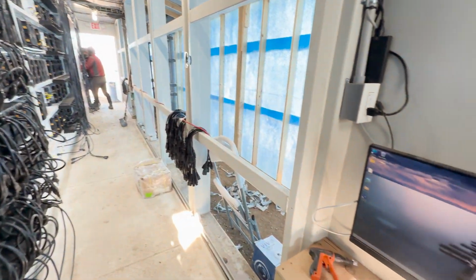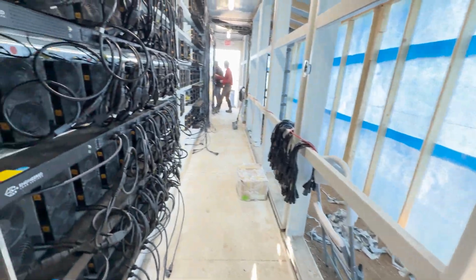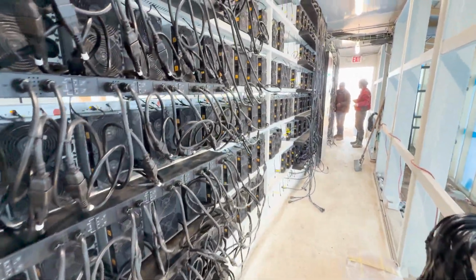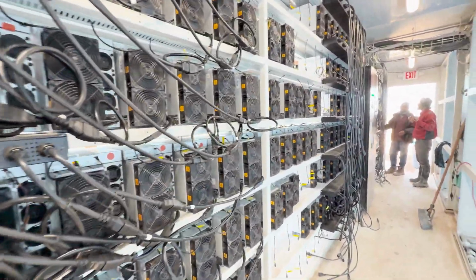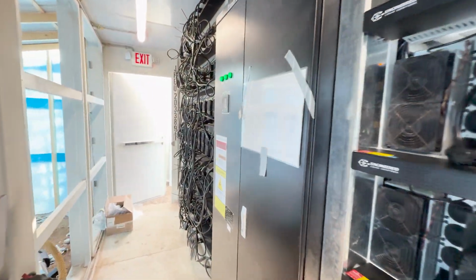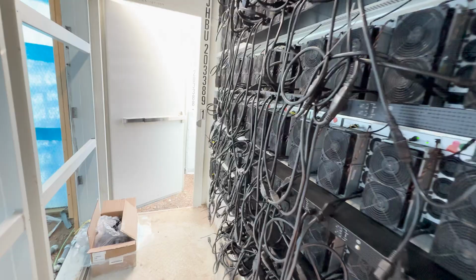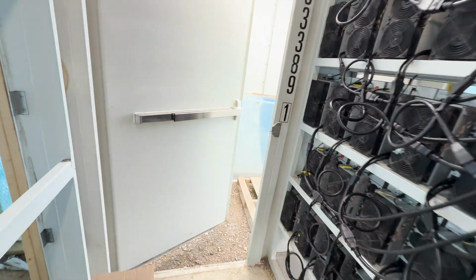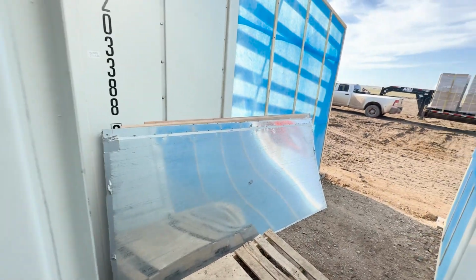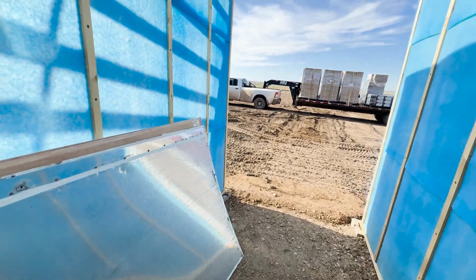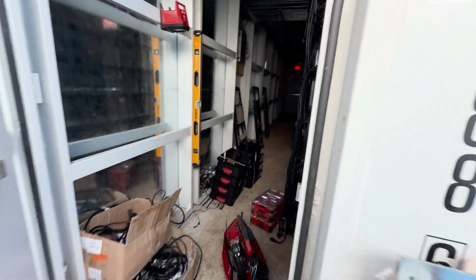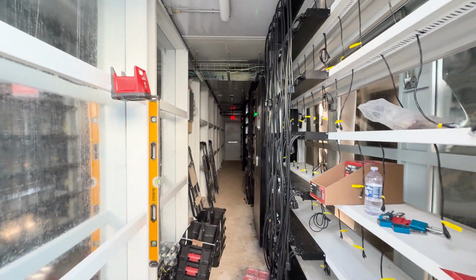Then the PDUs, they don't meet the AIC rating, so I had to swap those out. Again, we had to go back to the manufacturer of the PDUs and talk to them. For them, it was crazy because they really don't deal with anything like this, right? They don't sell PDUs or fuses because no one requests those. But they did request that in North Dakota. Looks like they're a little more strict here, but it is by the NEC code, the national electrical code. So we're all good there.